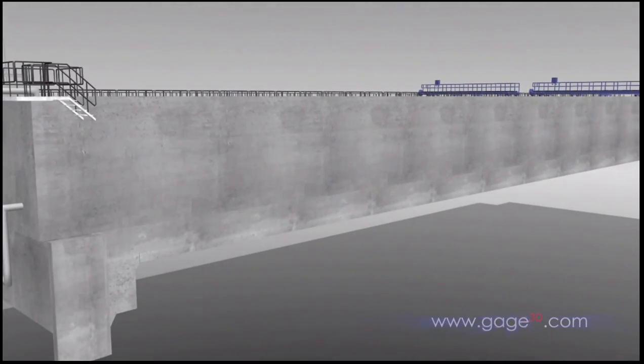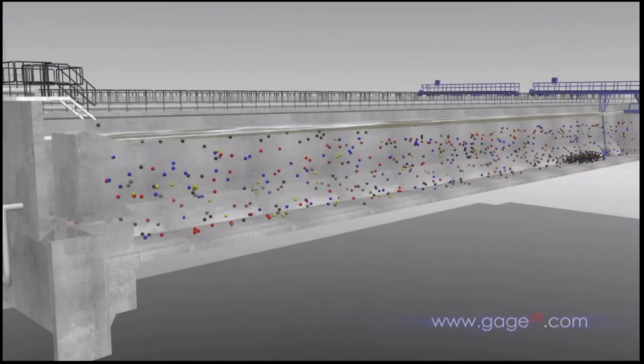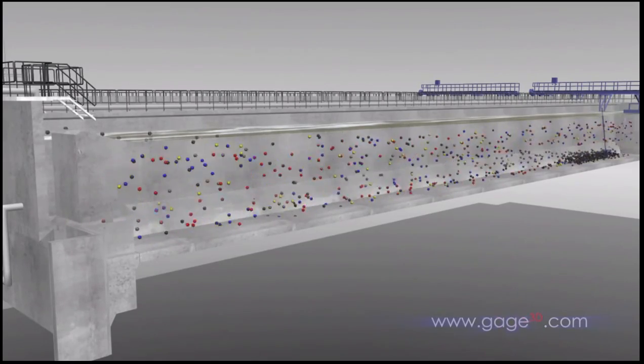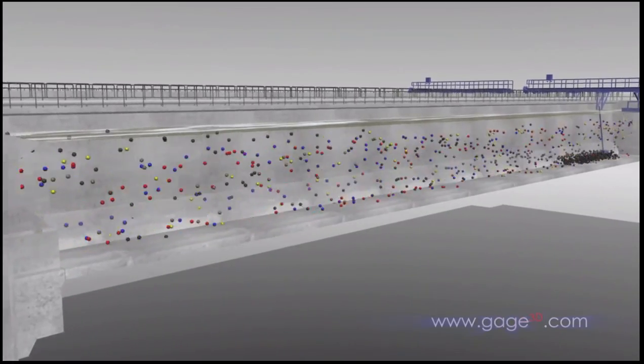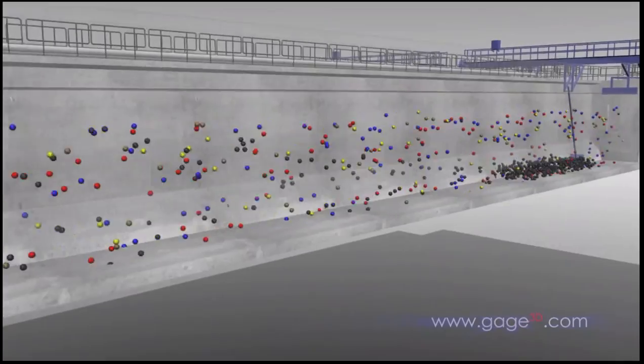The next stop within the headworks is the grit removal chamber. Grit is made up of large, heavy particles like sand or eroded cement. Water flows slowly through this tank, keeping organic matter like food, waste, bacteria, or excrement in suspension, but giving the heavier grit a chance to fall to the bottom.